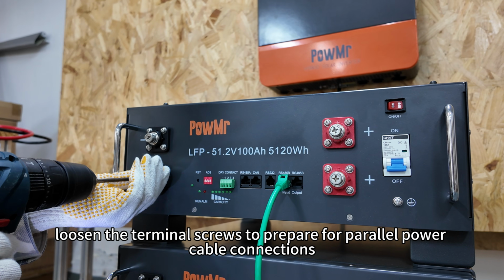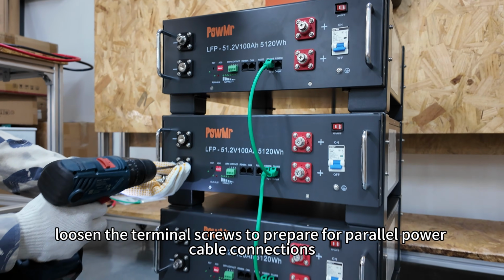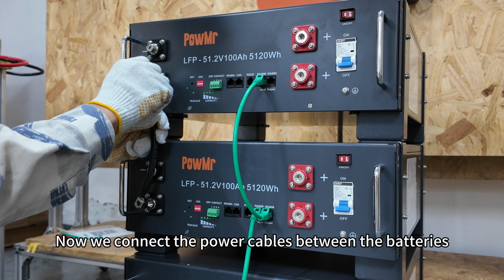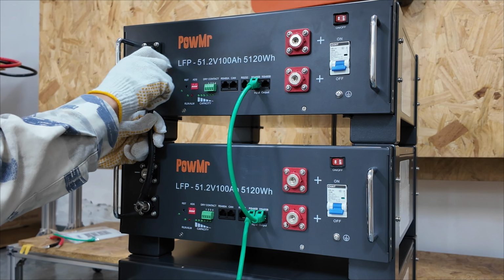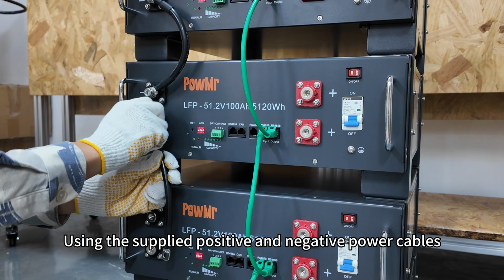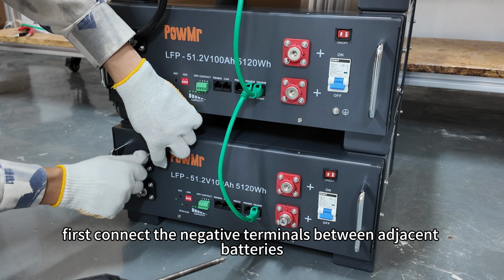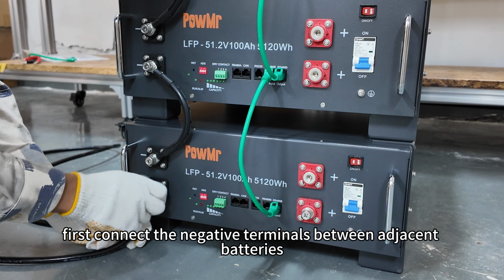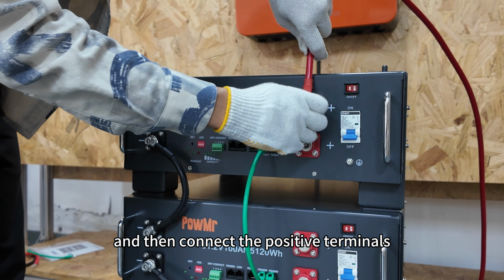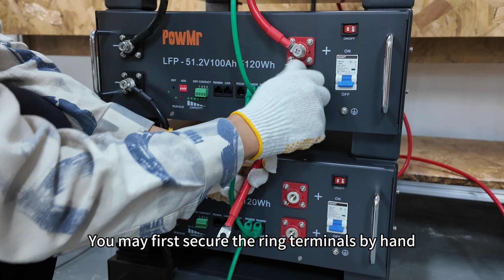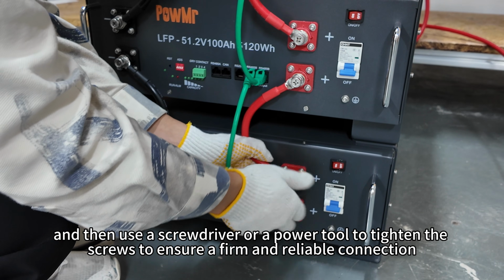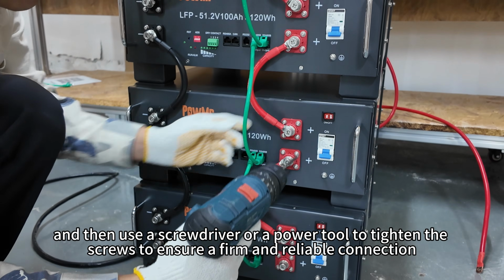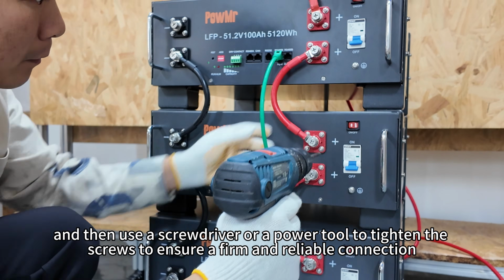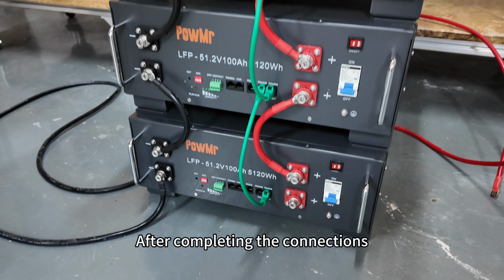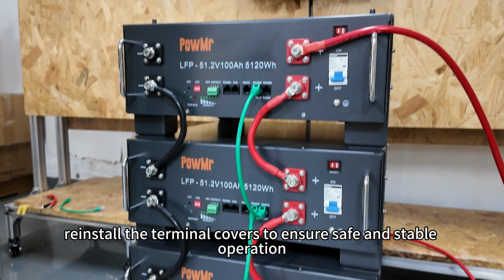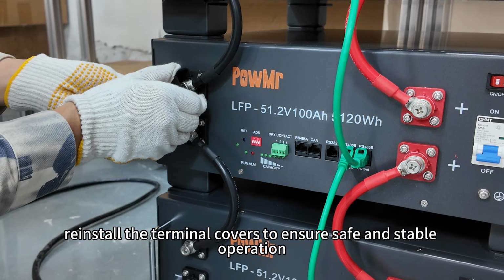Next, loosen the terminal screws to prepare for power cable connections. Now we connect the power cables between the batteries. Using the supplied positive and negative power cables, first connect the negative terminals between the adjacent batteries, and then connect the positive terminals. You may first secure the ring terminals by hand, and then use a screwdriver or a power tool to tighten the screws to ensure a firm and reliable connection. After completing the connections, reinstall the terminal covers to ensure safe and stable operation.